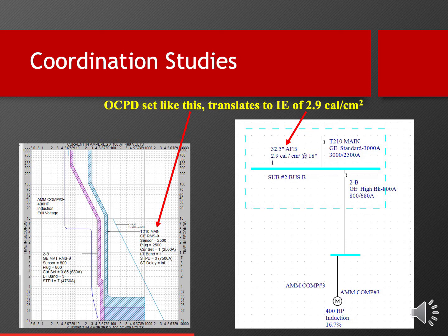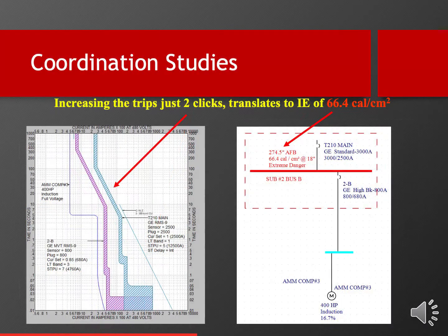Now, what I'm going to do here is simulate somebody doing something stupid out in the field. In particular, if they get what they think is a nuisance trip, they could change the overcurrent trip settings on that breaker, and I want you to see what happens. Let's go to the next slide. Now, this would occur if somebody had what they thought was a nuisance trip. In other words, sub 2 bus B tripped out, and they thought it was a mistake, that there really wasn't a fault, that the system tripped out accidentally.